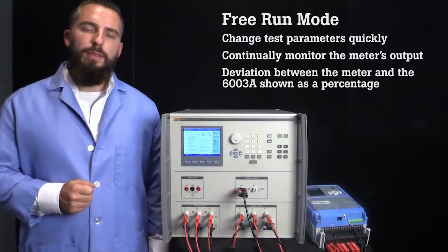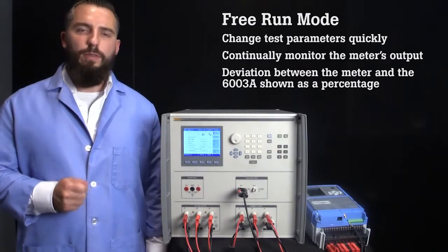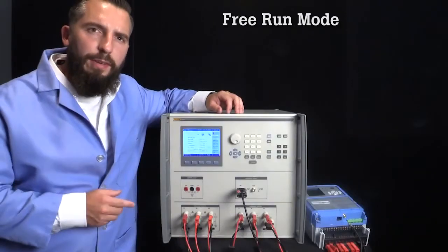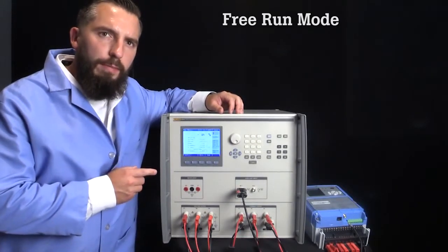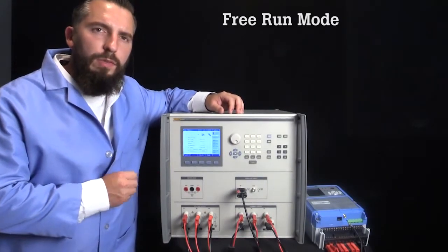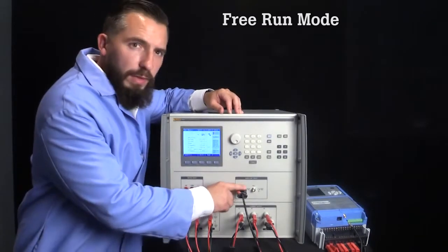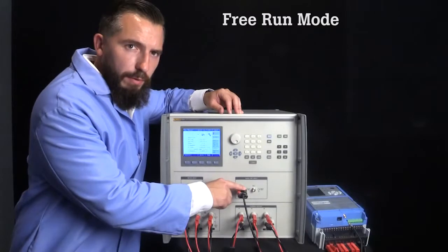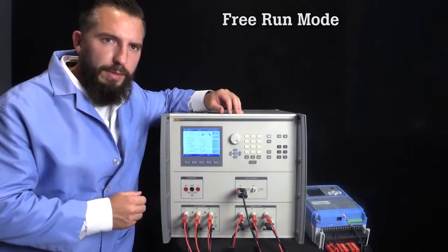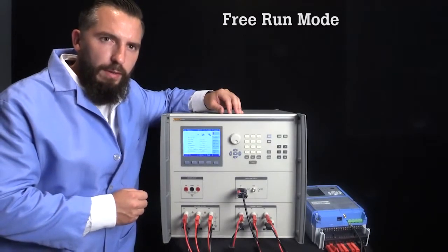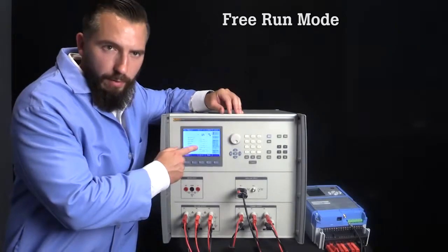The deviation between the meter and the 6003A is continuously calculated and shown as a percentage on the display. To demonstrate, I've configured a test for 200 volts AC, 1 amp, at 50 hertz. Since we'll be measuring the pulse output of the meter, I've connected the pulse output of the meter under test to input 1 of the 6003A. I need to set the meter constant or frequency to match the meter's pulse output, which for this meter is 6400 pulses per kilowatt hour.